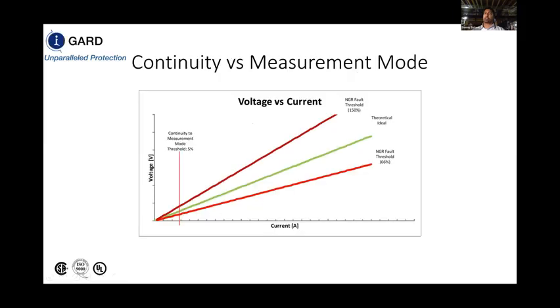And we have 2 different modes of operation: a continuity mode and a measurement mode. In continuity mode, we're constantly injecting that high frequency AC injection to confirm that the NGR is still able and still within the system. When we get into measurement mode, that's when we're detecting some voltage and some current on the neutral. That allows us to back calculate what the resistance is at the neutral by dividing voltage over current.